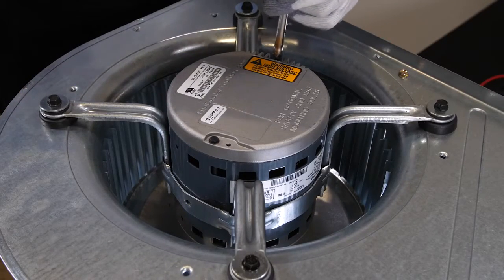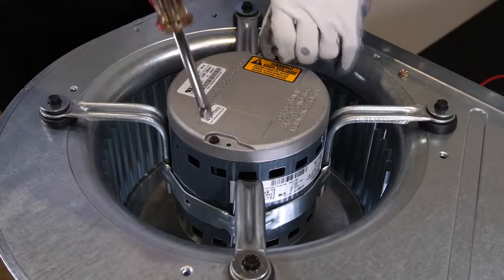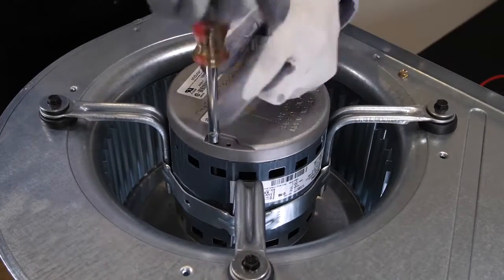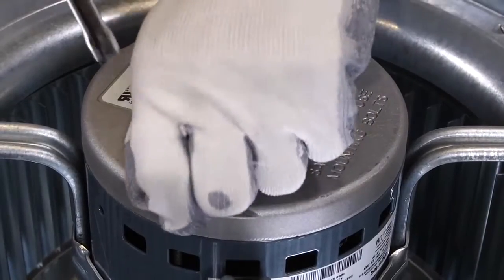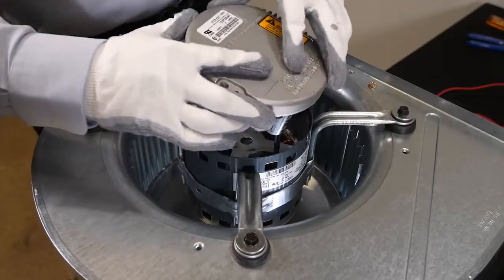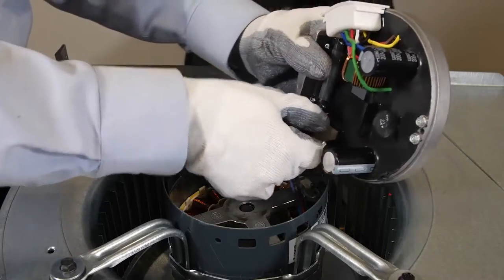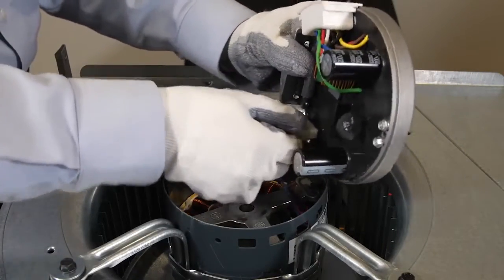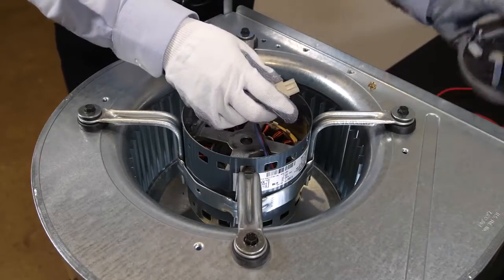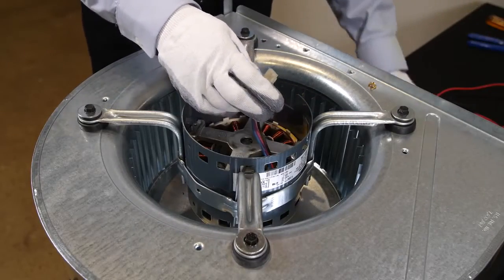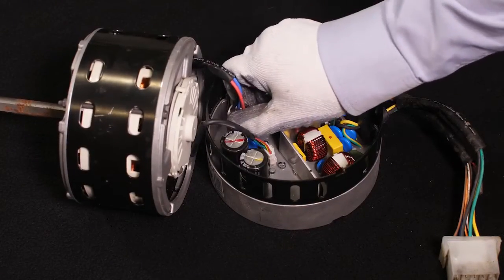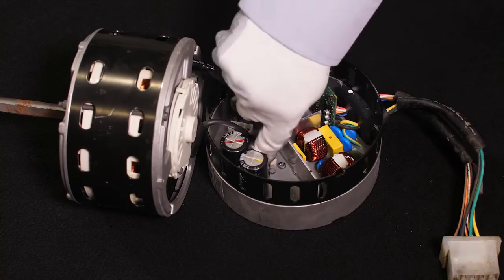Typically, the control module can be removed without removing the motor from the blower assembly. Remove the two control module mounting screws and separate the control module from the motor. Disconnect the three-pin motor connector from the existing control and be careful to depress the latching mechanism before pulling the connector away from the control. Avoid pulling the wires. Depending on which type of tap-select ECM motor you have, you may have an additional plug to remove.